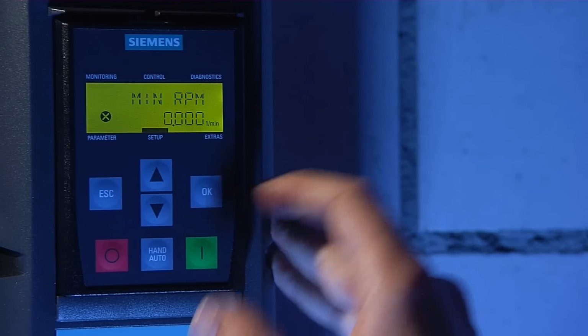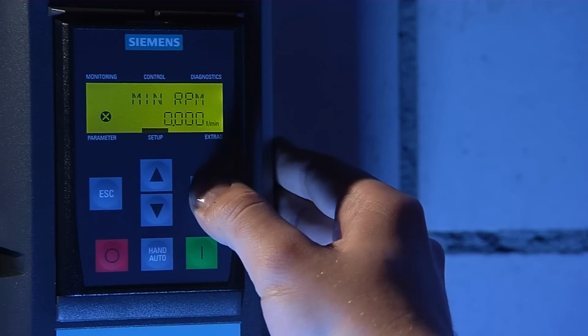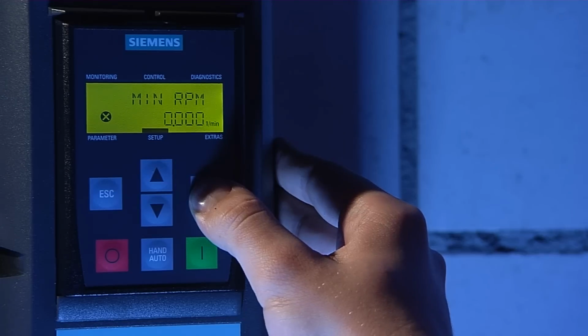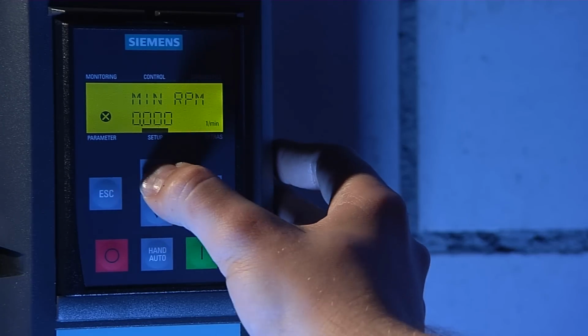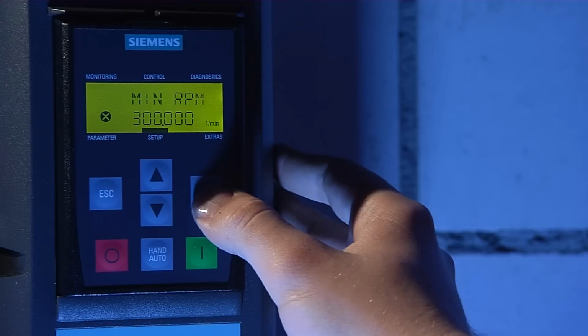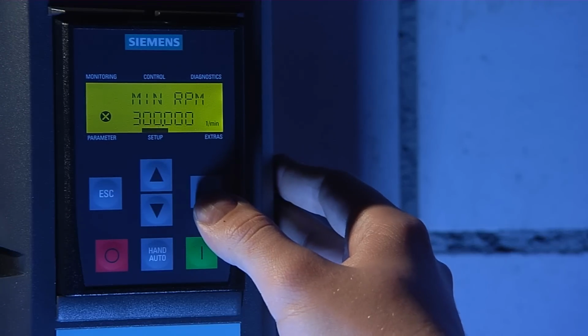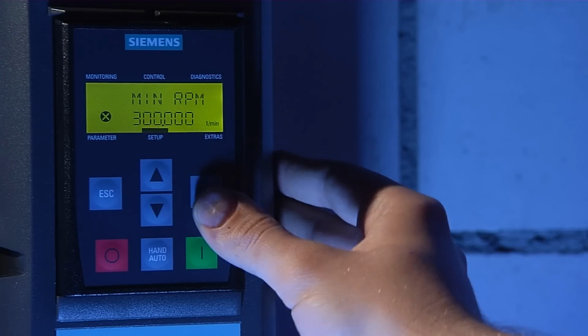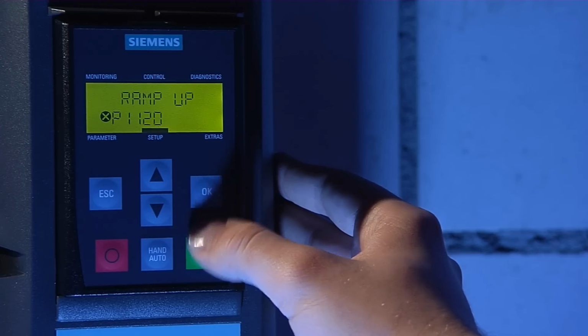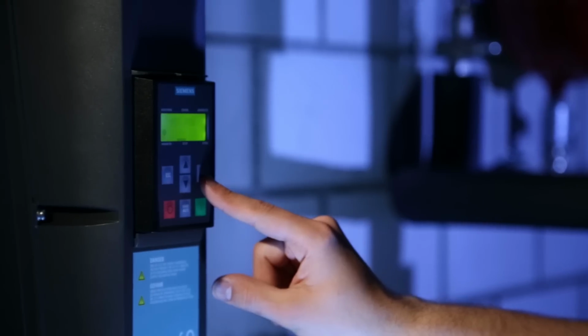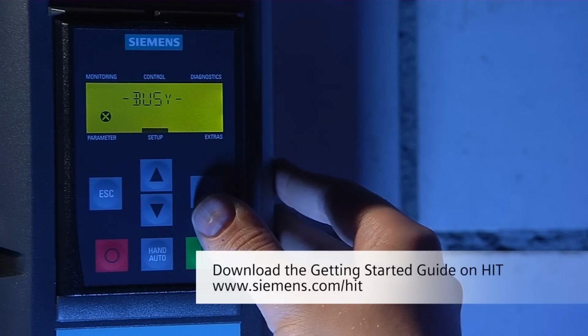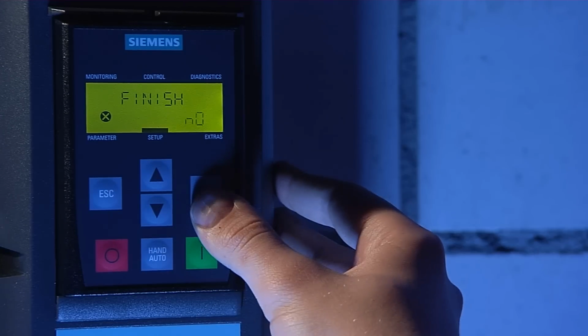For most applications, a minimum motor speed of 20% of the maximum motor speed is a safe value. In our example, that would be 300 revolutions per minute. In the next two steps, set the ramp up and ramp down times suitable for your application. The Siemens recommendations for the most common HVAC applications can be found in the Getting Started guide, included in each bundle. The next step is the last step.